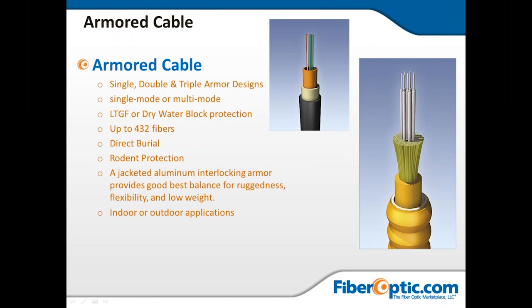Here's an example of armored outdoor cable. You can have single, double, or triple armor designs — an external armor layer on the outside and possibly another layer on the inside. These are generally used for aerial lashing, direct burial underground, or lashing to a cell tower. Armored cable also provides rodent protection — it'll take a long time for them to chew through it. They also typically include dry water-block protection or gel filling to keep water from ingress.